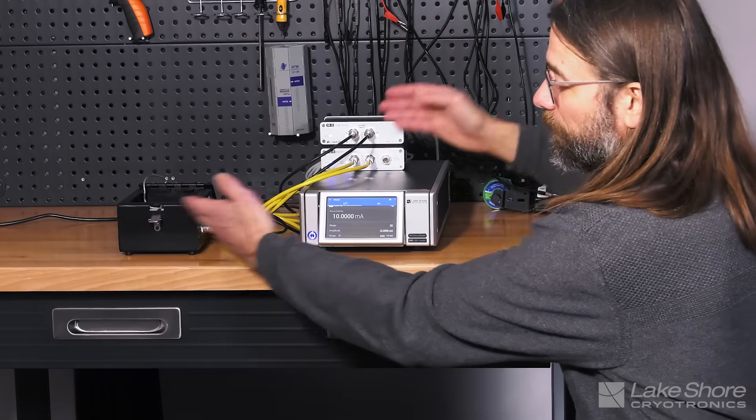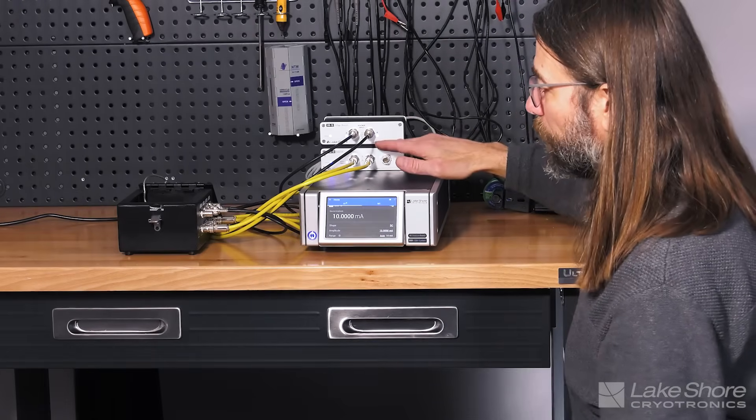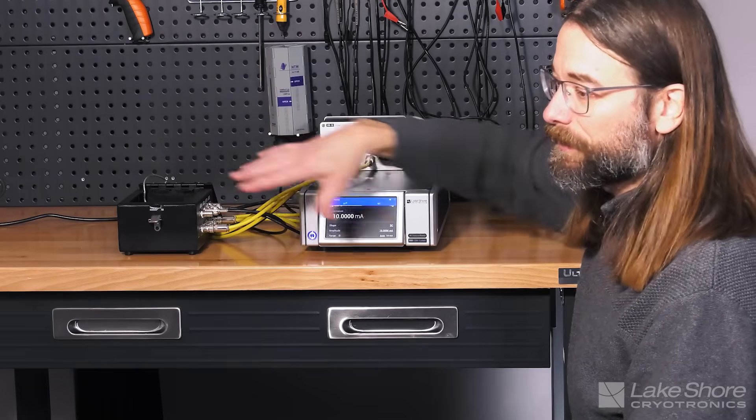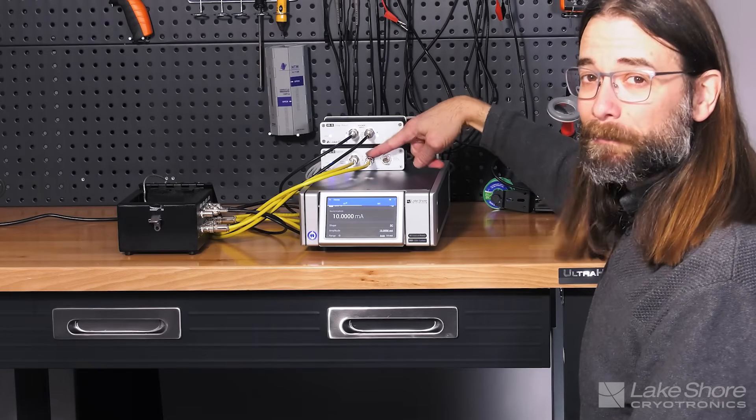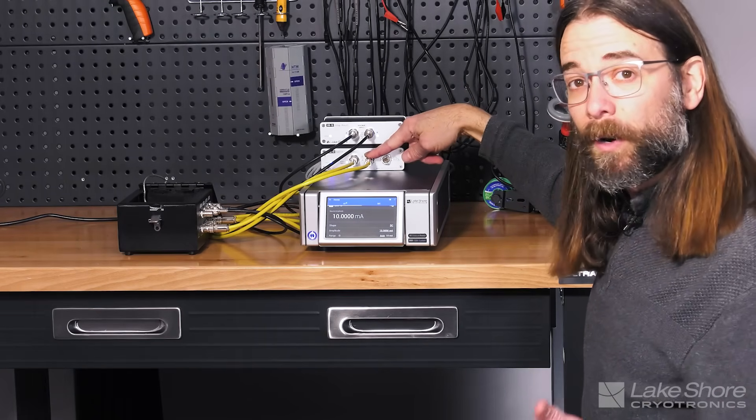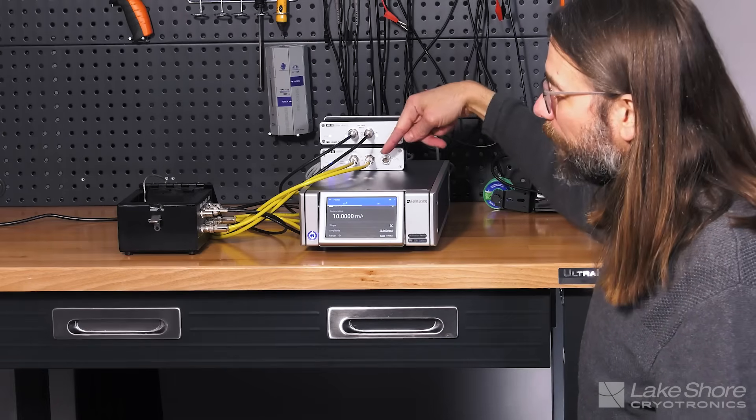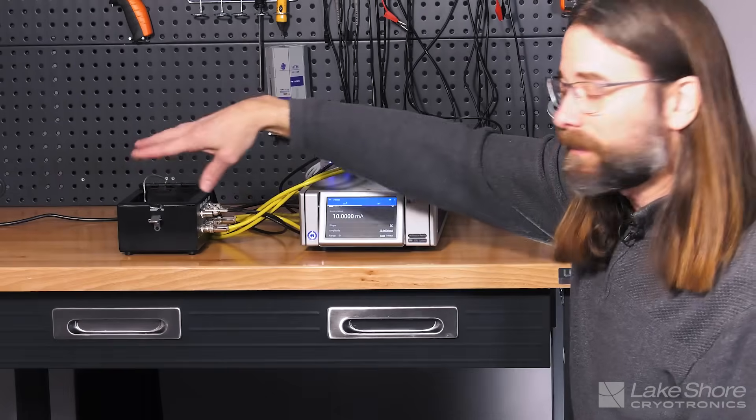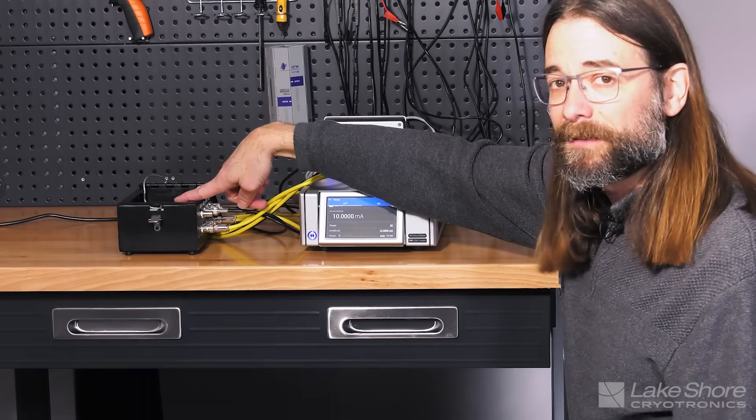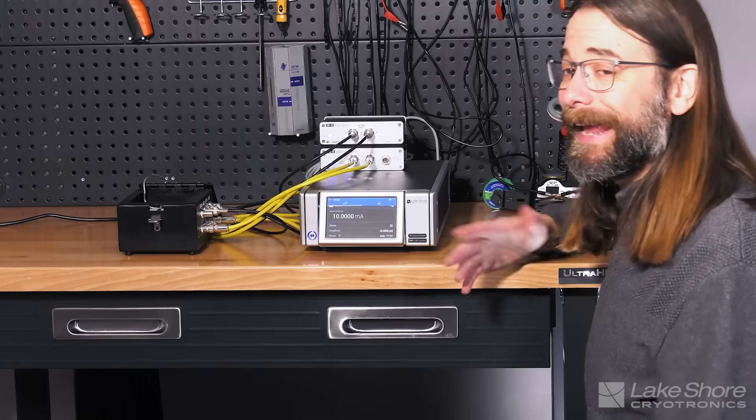So if we had really long leads separating our current source from our device under test, and we were making the measurement back here in what's typically called a two-wire measurement, if we were making our voltage measurement here at this end, we would have the voltage drop of all of that lead and contact resistance leading to the device under test in both directions. So that's going to add more error.